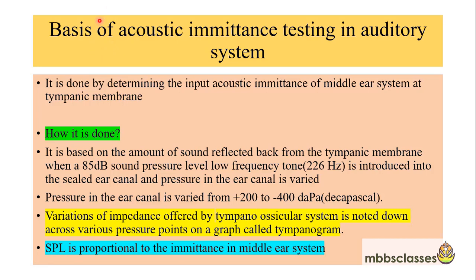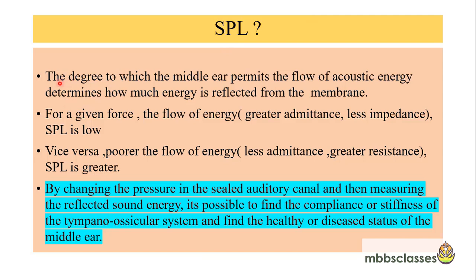The basis of tympanometry is the calculation of impedance by measuring the SPL. If energy is flowing freely through the tympano-ossicular chain, then very little energy will be reflected back. So SPL is proportional to the immittance in the middle ear system. The degree to which the middle ear permits the flow of acoustic energy determines how much energy is reflected from the membrane.